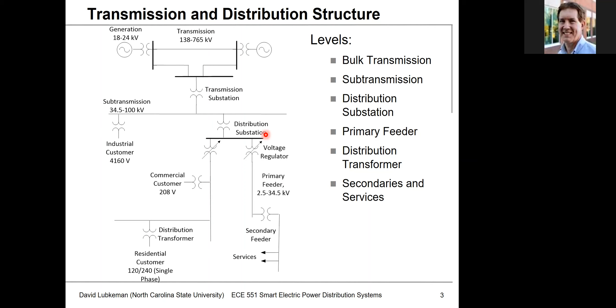First, at the top of each circuit, we have a distribution substation. The distribution substation converts the transmission level voltage down to distribution level, down to the 4 to 40 kV range I mentioned before. There are a number of different components in a substation, which I'll get into shortly. There's a lot of focus on substations because there are so many components and it's such a critical part of our system.